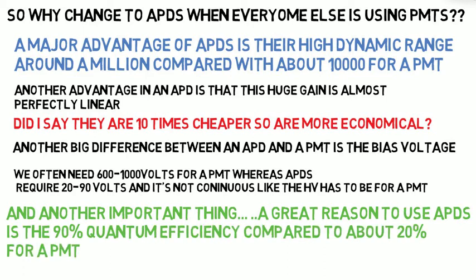Another big difference between an APD and a PMT is the bias voltage. PMTs typically require around 1,000 volts, whereas APDs are about 20 to 90 volts, and it's not continuous like the high voltage has to be on a PMT. The big deal for the latest APDs is their amazing quantum efficiency — near 90% compared to maybe 20% for a PMT.